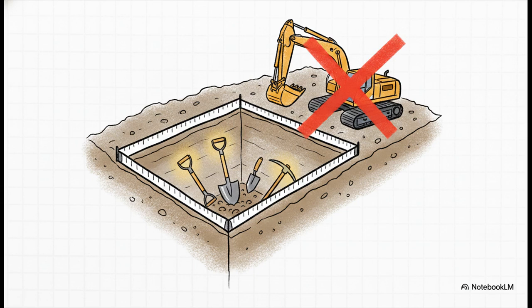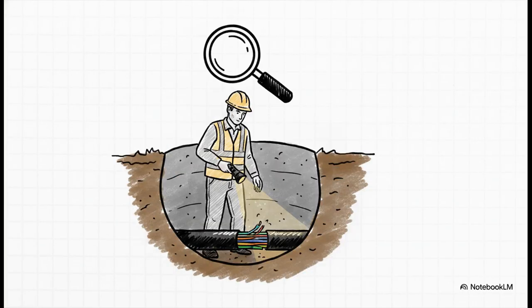And this brings us to the exact physical dimensions of the trial holes themselves. The regulations lay it out clearly: contractors must dig manual trial holes with a minimum width of 1 meter by 1 meter and a minimum depth of 1.5 meters. And this is crucial, so listen up: this must be done using hand tools only. Let me emphasize that. A shovel, a trowel, a hand probe, that is it. Heavy machinery is completely prohibited from operating near the marked route until this precise space is fully cleared and verified by hand.